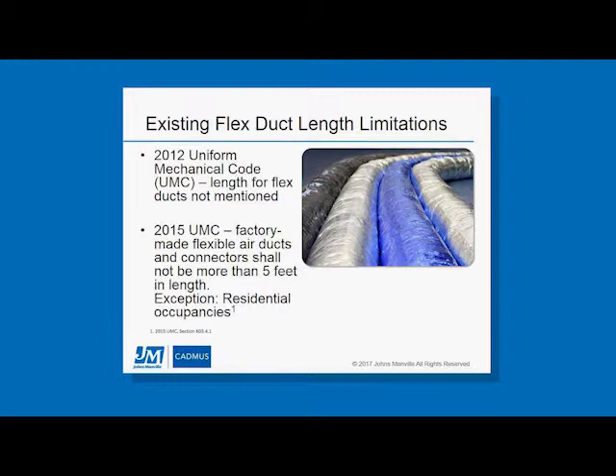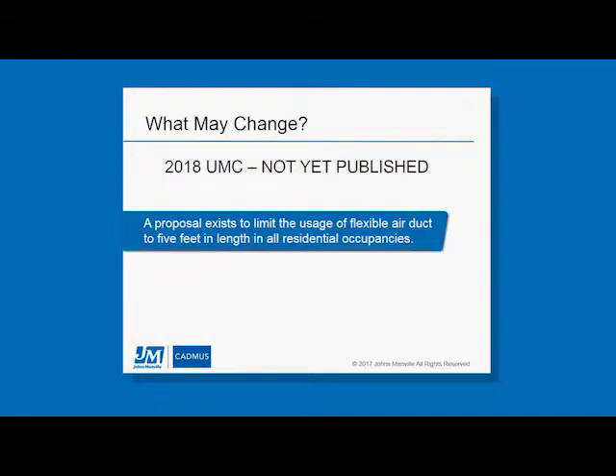So the code change in 2015 of commercial buildings, there was an exception that there was not a restriction on the length for flex duct for residential occupancies. However, in 2017, there was a proposal that was going to limit the length of the flexible air duct and air connectors to no more than 5 feet in length for all residential occupancies.